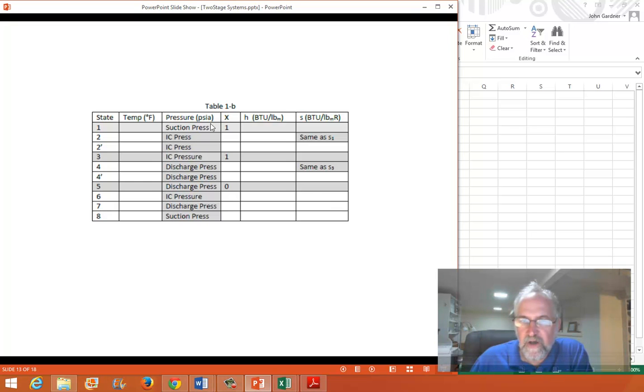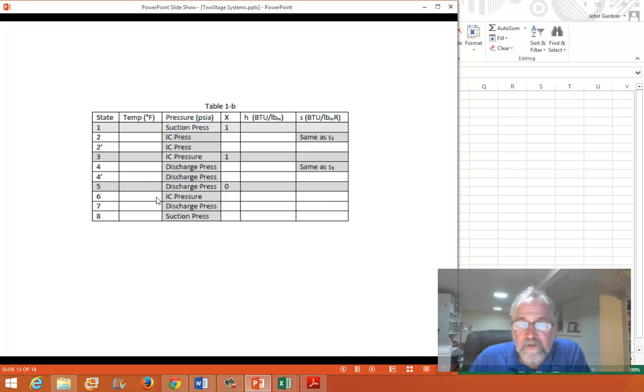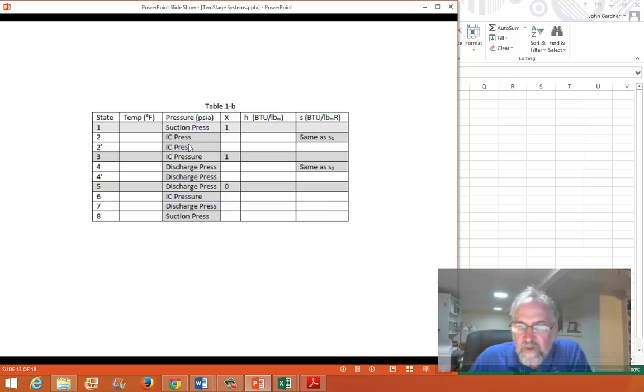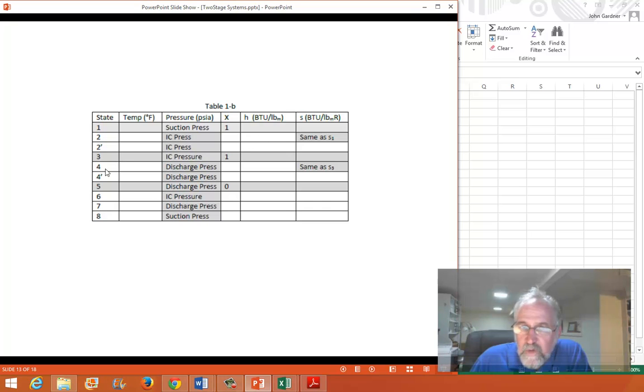The first step is to fill those three lines. Next, we know that states two and two prime are at the intercooler pressure — that's the discharge of the booster stage — and state three is also at intercooler pressure. States four, four prime, five, and seven are all at the discharge pressure. State six is at intercooler pressure — that's the small mass stream expanded through the valve into the intercooler — and state eight goes back down to suction pressure. We also know state two results from isentropic compression of the booster, so its entropy equals state one's entropy, and state four's entropy equals state three's entropy. For states two and four we now have two independent properties and can fill those out.